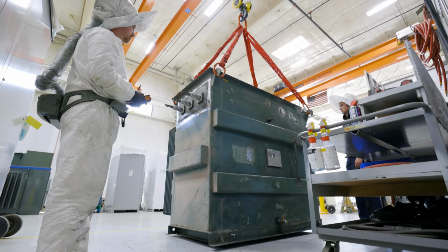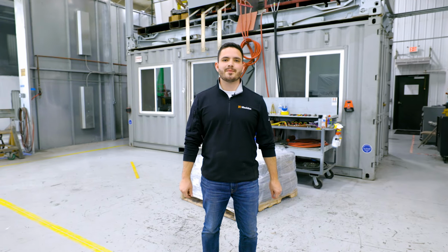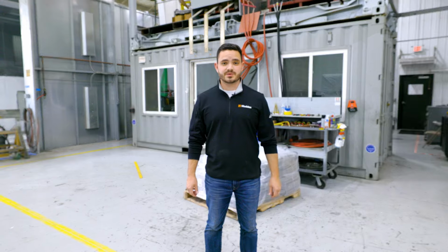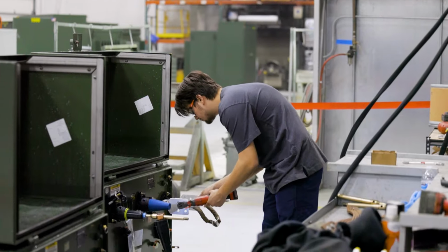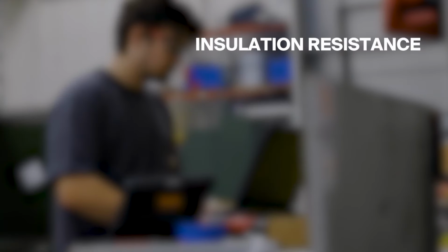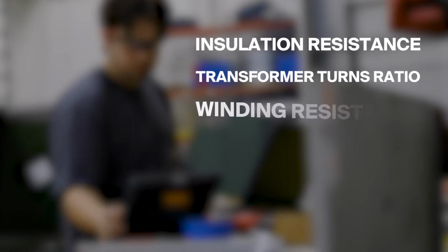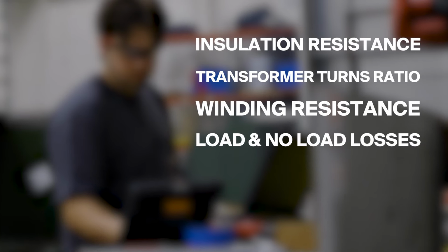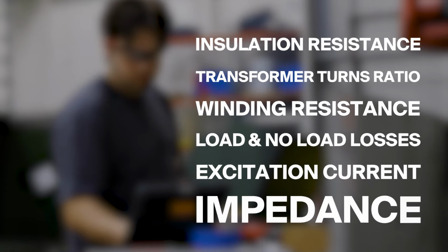Now that a transformer is reassembled, it goes to final testing. For final testing, we strictly follow the same IEEE C57 test procedures that new manufacturers follow. Other special tests like power factor and high pot can be made available upon request. This procedure includes insulation resistance, transformer turns ratio, winding resistance, load and no load losses, excitation current, and impedance.